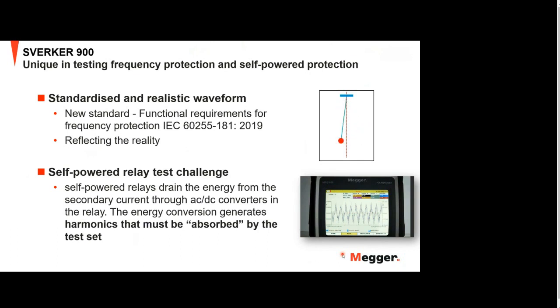Also, I will speak about how to test the self-powered relay, which is a challenge, because self-powered relays drain the energy from the secondary current through the AC-DC converter in the relay itself. The energy conversion generates harmonics that must be absorbed by the test set. So that's the challenge when you're testing self-powered relays, because it takes the power from the current transformer and it needs this current not only for measuring, it needs it also to be live and be able to work.